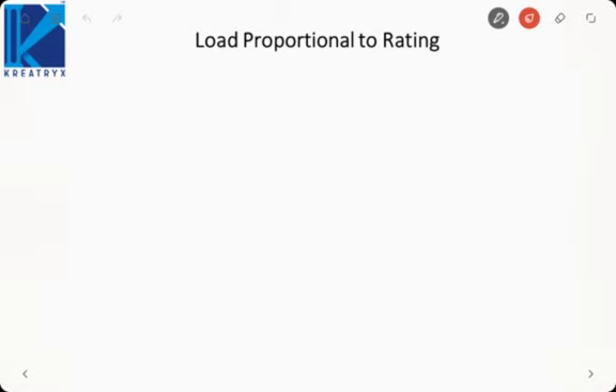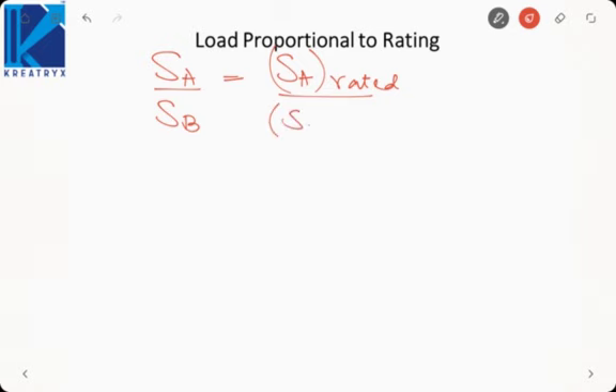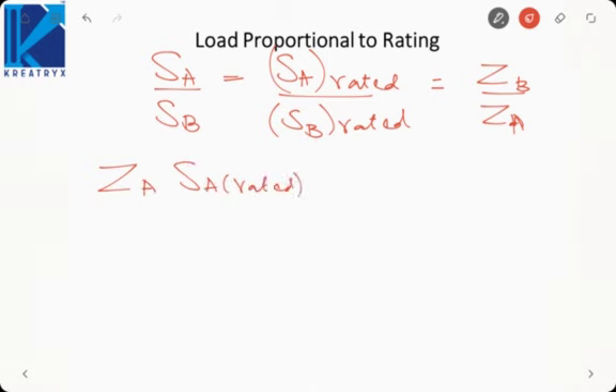Next, let us see, one of the desirable conditions was that the load sharing must be proportional to the kVA rating. So how can that be possible? What I am saying is, SA by SB should be equal to SA rated by SB rated. Now just now we saw that SA by SB would be equal to ZA by ZB. Sorry, it is inversely proportional to their impedances, so this will be ZB by ZA. Let us say these both are in ohm. So what I can say is ZA into SA rated should be equal to ZB into SB rated.